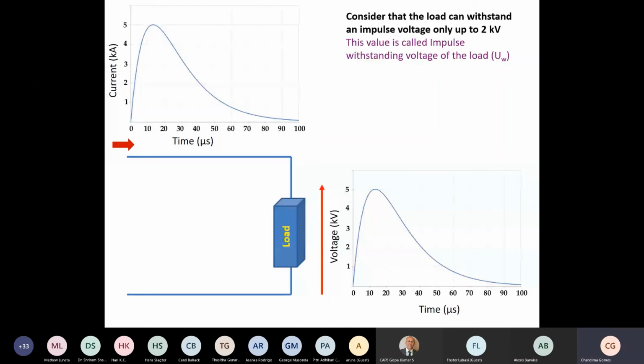Now consider a load which can withstand an impulse voltage up to about 2 kV. This value we call the impulse withstand voltage of the load. Usually when you're buying a load, these specifications are there if that equipment is according to proper standards. And definitely in this case the load will be damaged because it can withstand only 2 kV and the voltage goes to 5 kV.